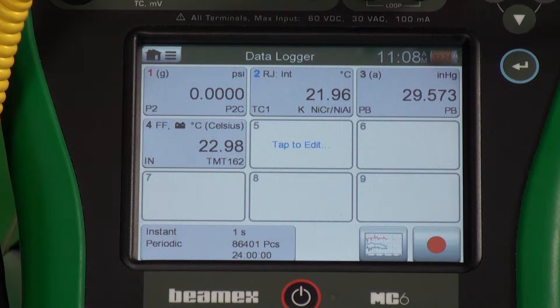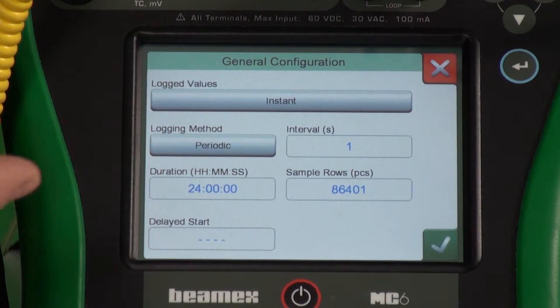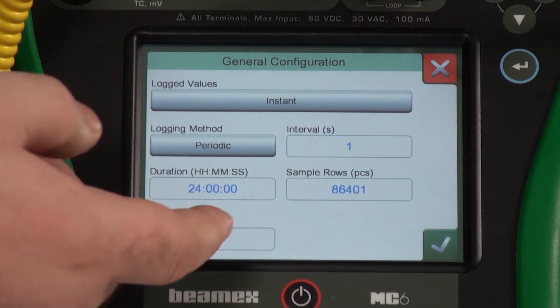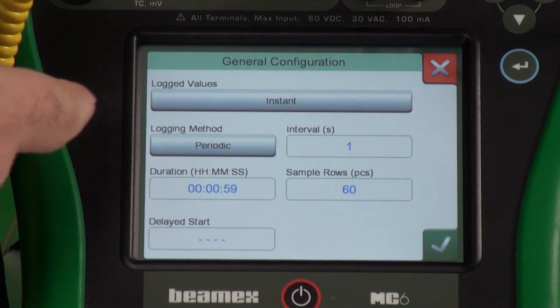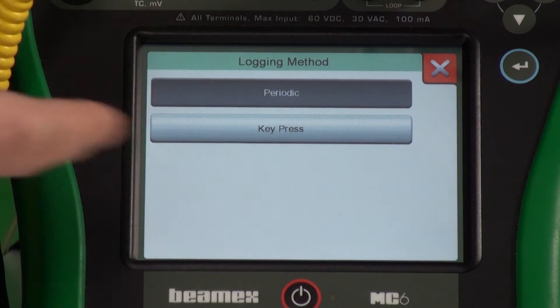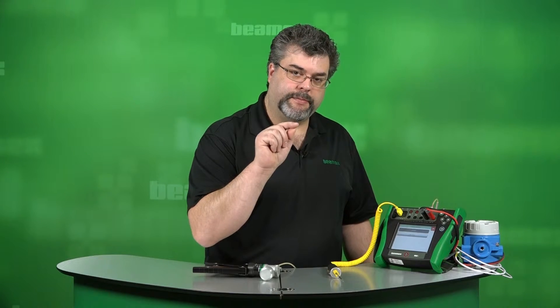At the bottom left is where we define how long we want our sample size to be and how often to grab those samples. Our last run was 24 hours with a sample every second. We can change this to be one minute long, or we can come here to the sample size and just say I want 60 samples, so it will automatically fill out the time for us. The logging method can be periodic — every second or every minute, however you define — or you can set it to every time you press a button it will capture the data. That's key press.